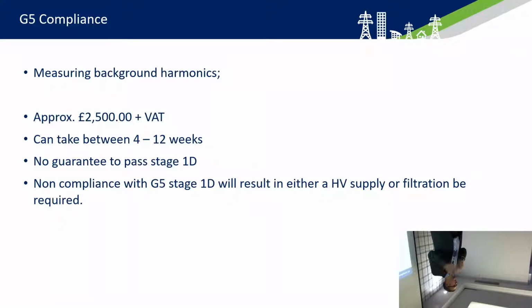So if I don't have one now and I've got harmonic problems, am I not caused by someone else? Possibly, yeah, but you've got to pay for it if you put a measurement on your supply and that was showing over 5%. The power quality recorders will tell us which direction the harmonics are flowing - so if we put a power quality recorder on, we know whether it's your equipment causing the problem or whether it's the grid causing the problem. If it was the grid, we'd have to rectify it. If it was you causing the problem, we'd give you that report and say we need to look at what equipment you're using and address it that way.